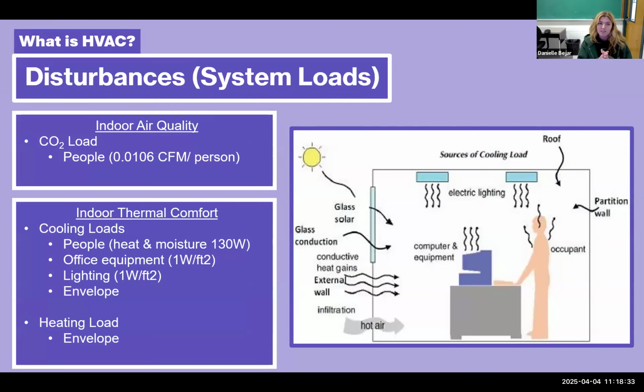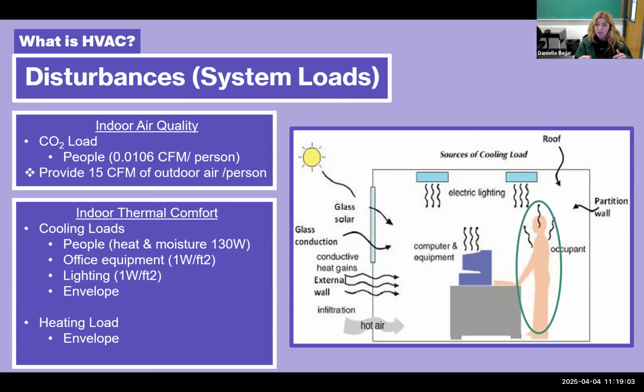So we know our desired conditions: CO2 levels less than 1,000 ppm, 75 degrees Fahrenheit, 50% relative humidity. Now, what kind of disturbances are there taking us away from those desired conditions? These would be our system loads. First, looking at indoor air quality, we have our CO2 load, that's people. People generate about 0.0106 CFM of CO2 per person. To mitigate those effects, our HVAC system has to provide about 15 CFM of outdoor air per person. And then looking at indoor thermal comfort, we have cooling loads and heating loads. Here I want to be clear: a cooling load is something that heats the space, so our system has to cool them. Same for heating load: these are things that are cooling our space, so our system has to heat them.